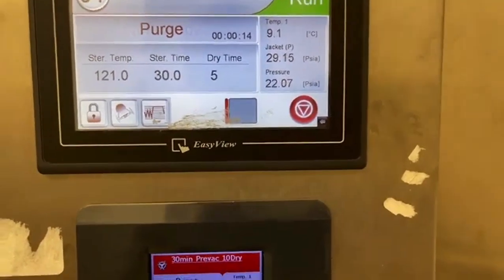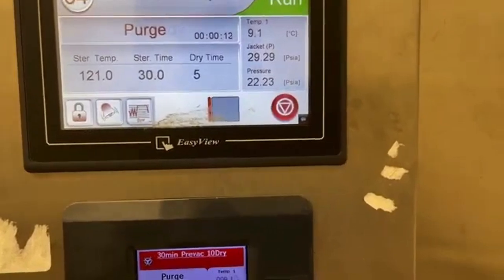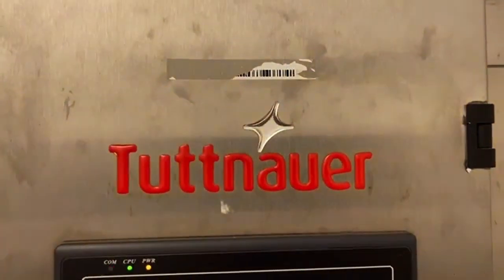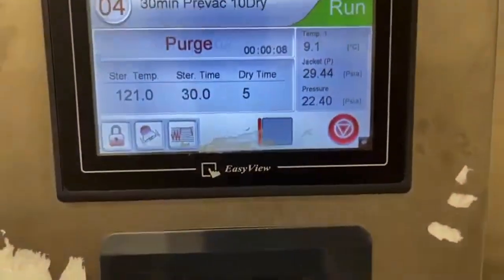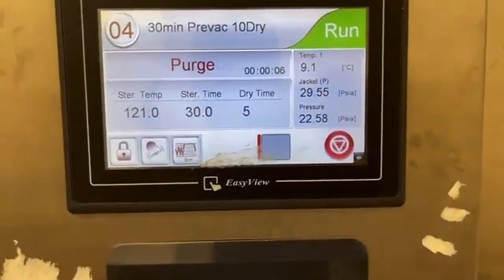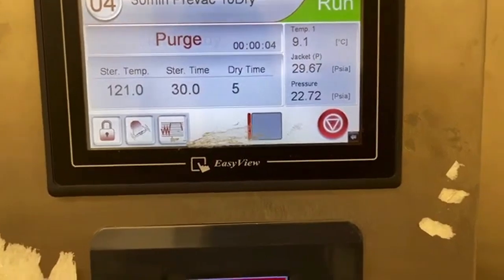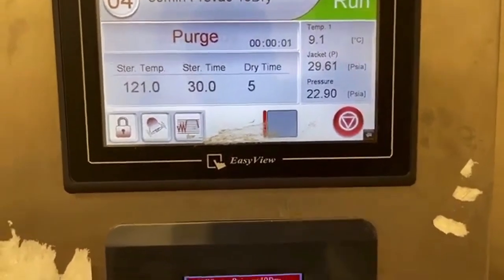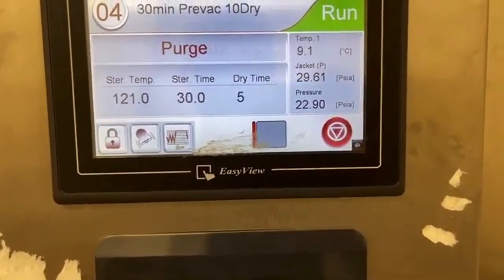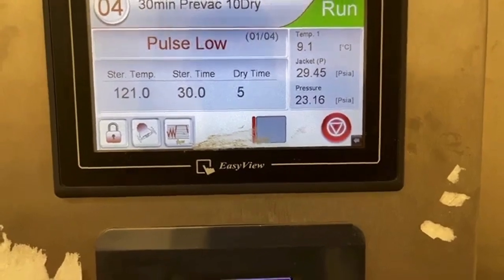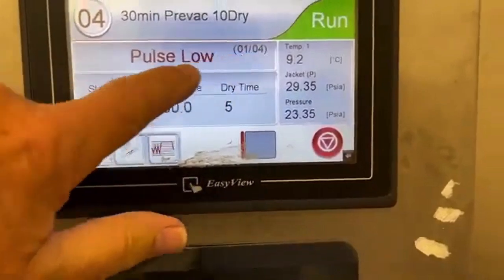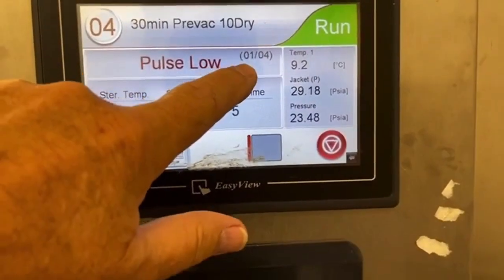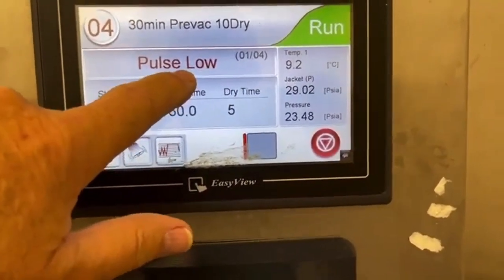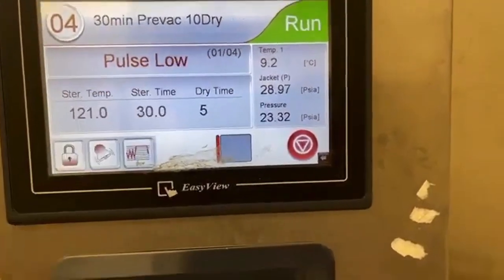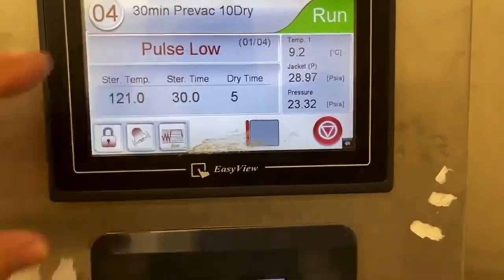The 4 pulses that I have set up for this machine, this is a Tuttnauer. This model is a 69-137 single door with load probes. But again, I'm not using the load probes as a control. But you can see here that we're on pulse 1 of 4. Normally you have 3, but for the animal carcasses, I wanted 4 pulses.